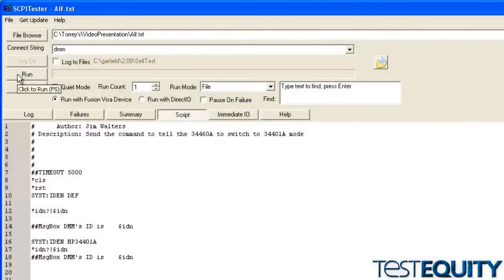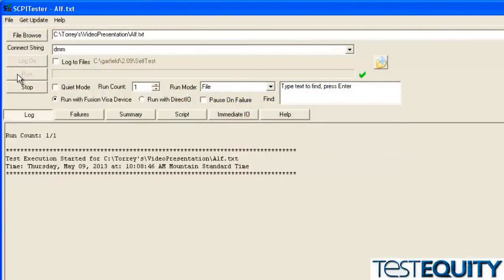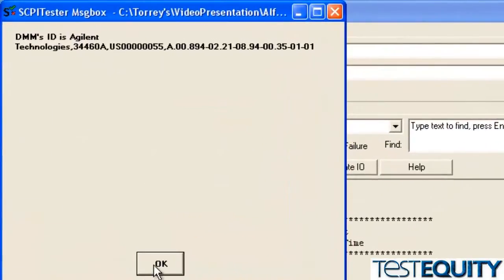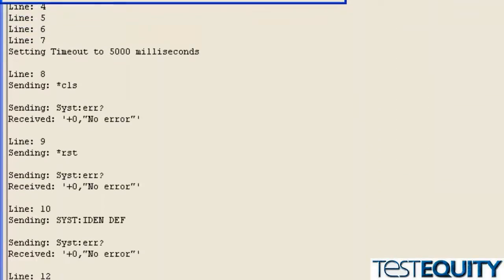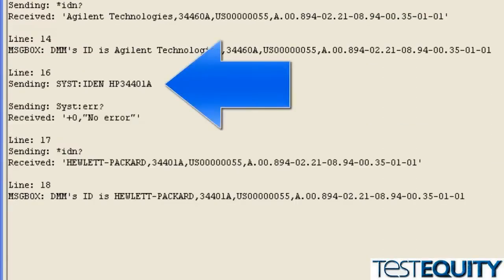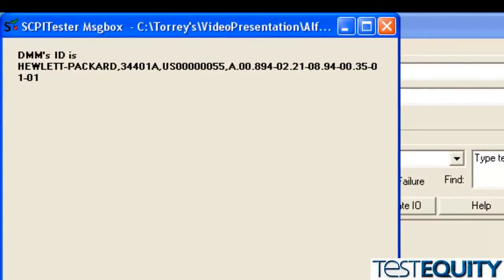Okay, now I've sent commands to the box asking what its identification is, and it's coming back and telling me that it's an Agilent 34460A. Now I'm going to reprogram it to be a 34401A for compatibility with older systems. And I've just sent the command, and I've asked the box what its IDN is, and it's coming back as a Hewlett Packard 34401A.